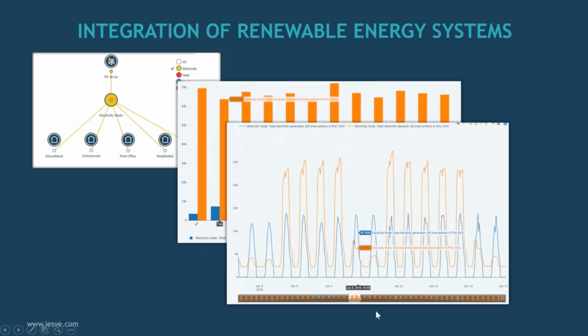So if we look at things at an hourly level, we can see that the blue line, which is the electricity generation, in some cases, for example here, if I'm not wrong, it's a weekend, a Saturday and Sunday, these 5 buildings are generating more energy than what is needed to run. So we are actually wasting energy at these particular times along the year. And at the end, it's a matter of trying to understand how much these values are along the whole year.